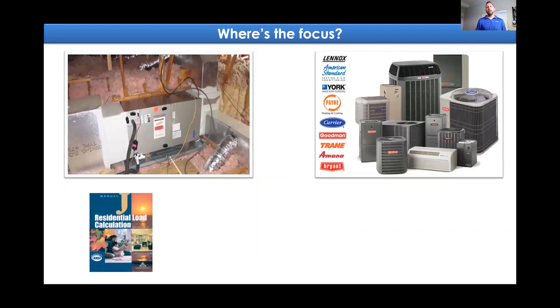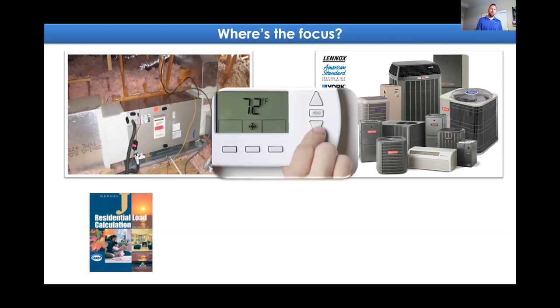That way we can have complete control of it. But here's where our focus is - our focus continues to be on our HVAC equipment. No disrespect to any equipment manufacturers, there's a lot of great high-end, energy efficient, modulating, multi-staged equipment that can do a fairly good job. But unfortunately, we still get a lot of calls saying, I've got that high-end system and it's just not achieving what I need for my comfort, health, or in some cases, preservation. So the typical homeowner will just continue to turn their thermostat down to try to offset that moisture feeling problem. And as I mentioned, the problem becomes: number one, we're outside of our design parameters, which is our manual J calculations, so now the air conditioner may not even work the way it was designed to. And secondly, we're offsetting one problem and creating another.